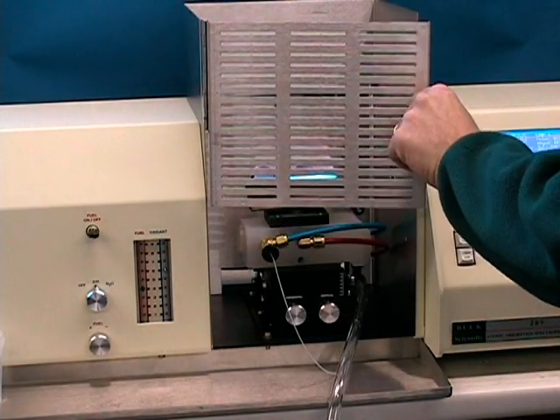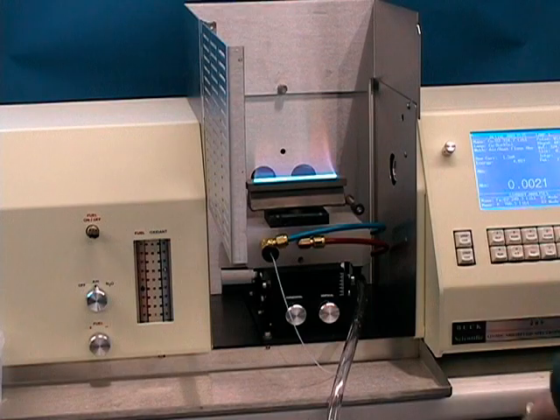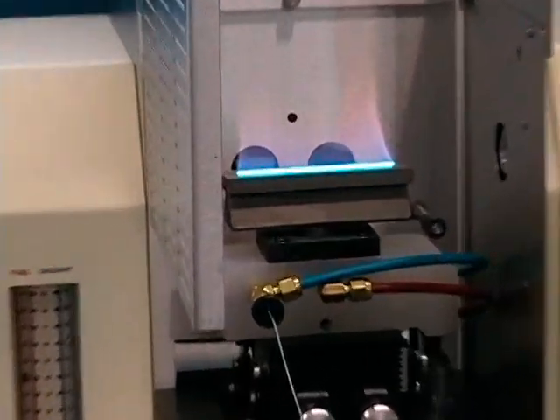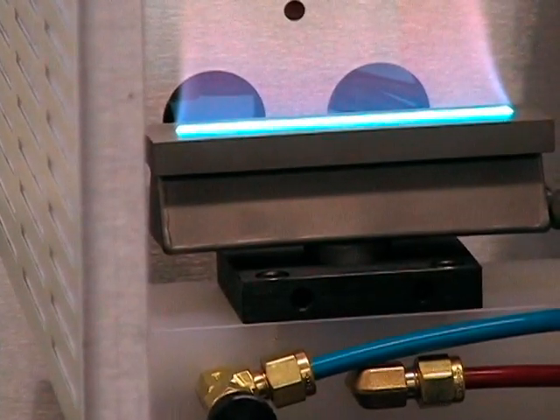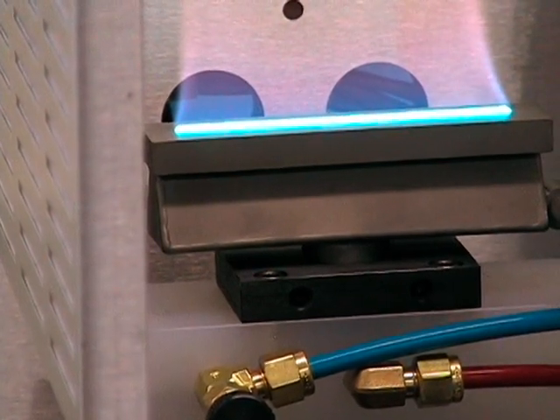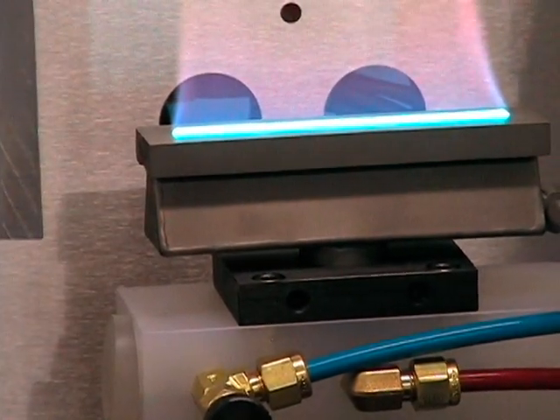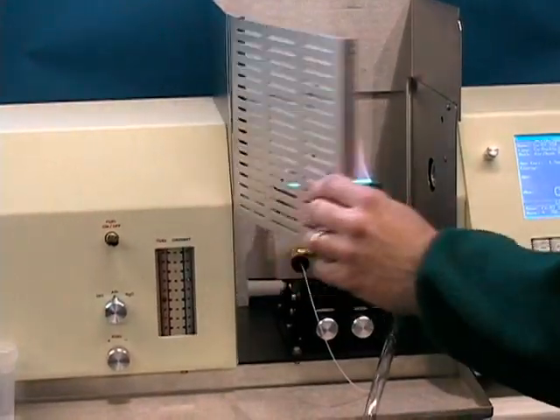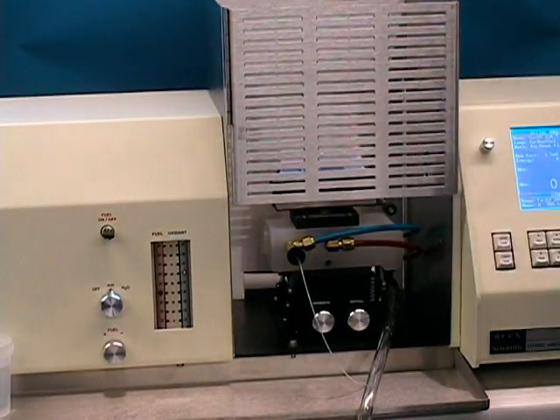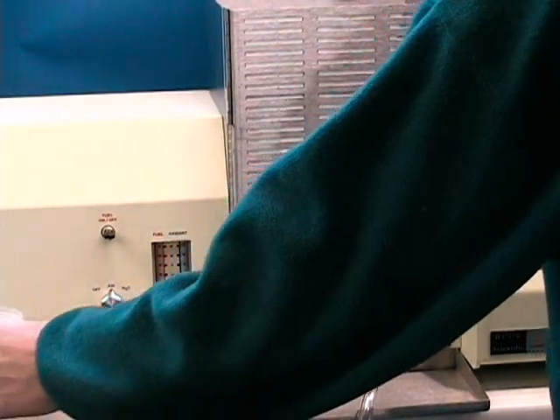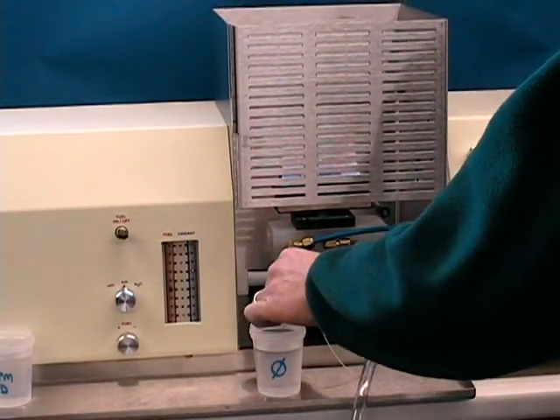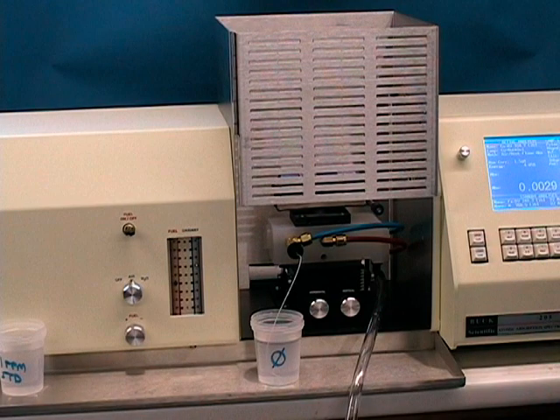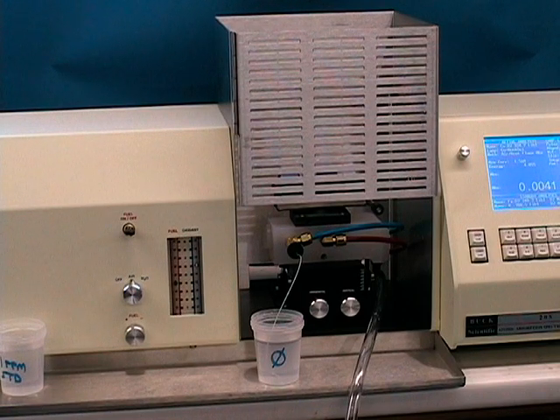The little blue feather that you get should be approximately 1 or 2 millimeters high for a typical flame, and only needs to be changed in the case of doing chromium, which requires a rich flame. At this point, close the burner shield and aspirate your DI water or dilute acid blank to keep the burner head cool. It is recommended that the burner not run dry for more than a few minutes because the heat may deform the polypropylene spray chamber after a while.